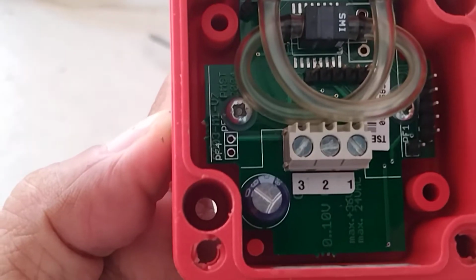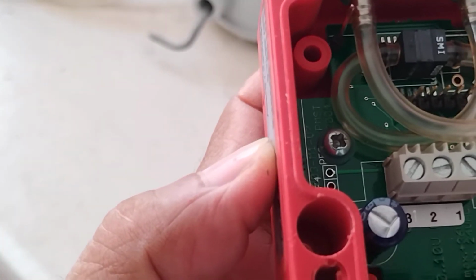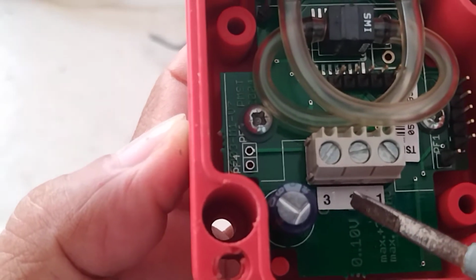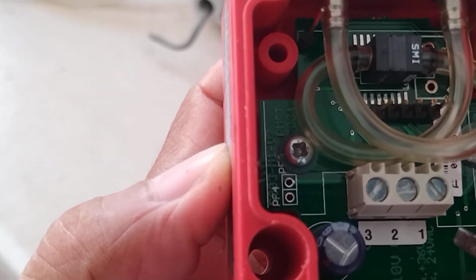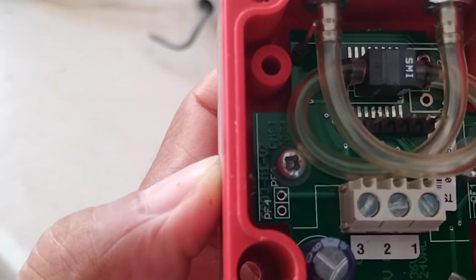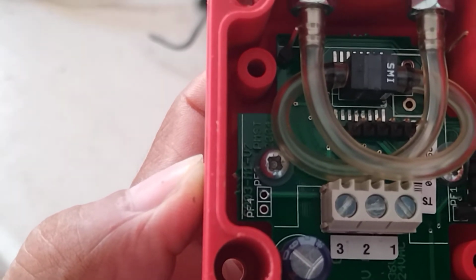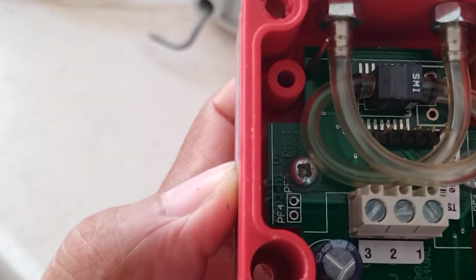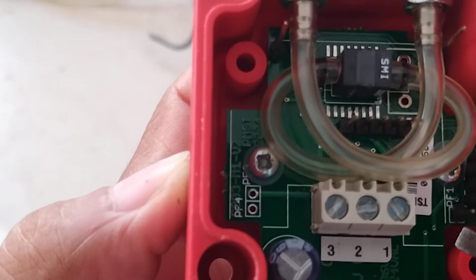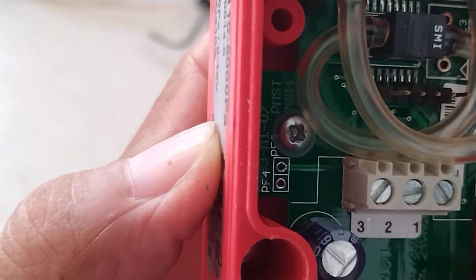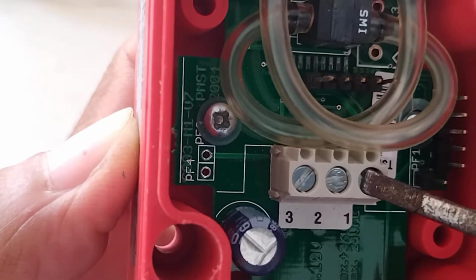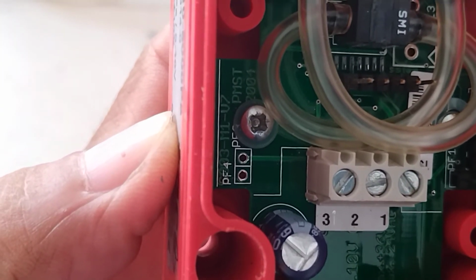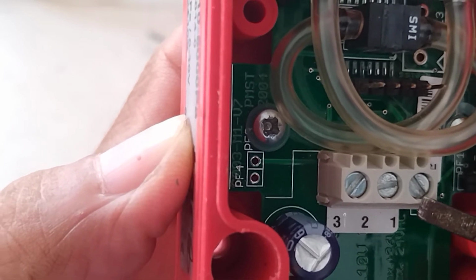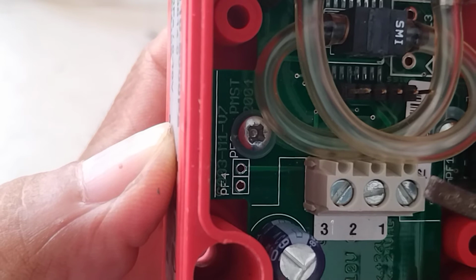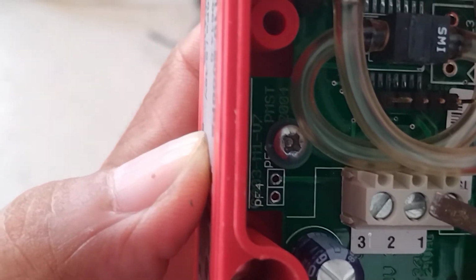Another thing you need to know, if you're the BMS engineer, BMS technician, foreman or supervisor, is what you need to provide before this device will give you the differential pressure for the equipment you are trying to monitor. For a differential pressure transmitter, you need to provide a power supply. In terminal 1, it says 24 volts AC, so your 24 volts AC wire will go here. Then the common will go to 3.